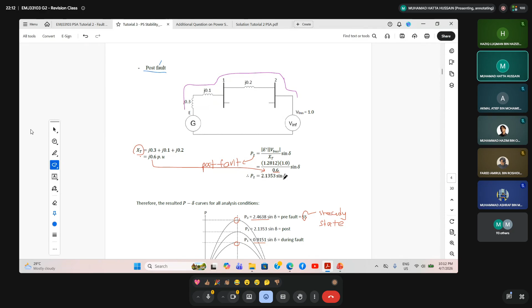Then, when we compare, you need to draw the power angle curve. When you draw the power angle curve, we can see that during the post-fault, the magnitude is in between during fault and before the fault occurs, which means the pre-fault or steady state. SS here means steady state condition before the fault occurs. You have to make sure your post-fault is in between. If you get more than this, it means you have made a mistake.